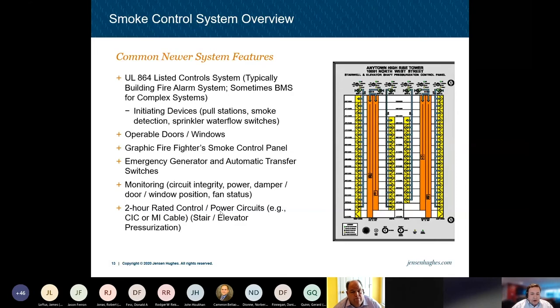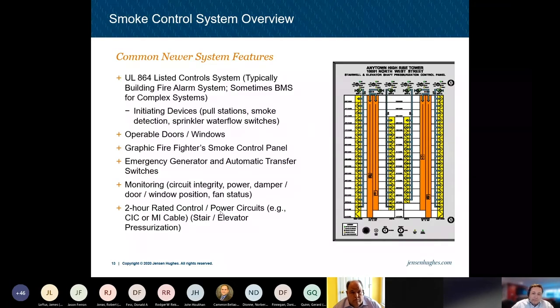The big one that comes obviously to the forefront in people's minds is the smoke control panel, the graphic firefighters panel that provides status and override of the equipment for the building. So you'll see on the right here, we have a figure where it has an elevation of the building. It shows stairs, hoistways, airflow paths, injection points. It has HOA switches, that's hand-off-auto switches with LEDs, indicating on, normal, off, and fault status for each equipment. And then you'll have a trouble horn on the panel. You'll have a lamp test, which you can press and illuminates all the LEDs on the panel. You'll have the overriding gauge, which is usually key to the local fire department. And then you'll have a legend on the panel that indicates what all the equipment and LEDs are for.